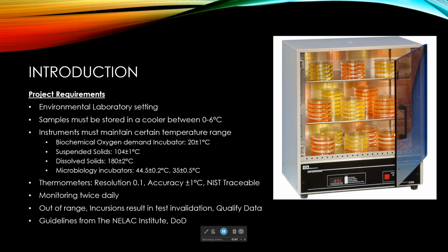The thermometers used for these instruments and environments have to meet certain specifications, like the resolution has to be 0.1, and accuracy has to be within 1 degree, and the thermometers have to be traceable. The temperature has to be monitored twice daily, and it should not go out of range.